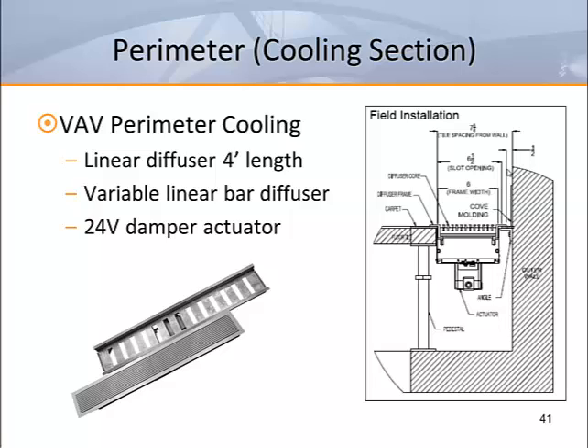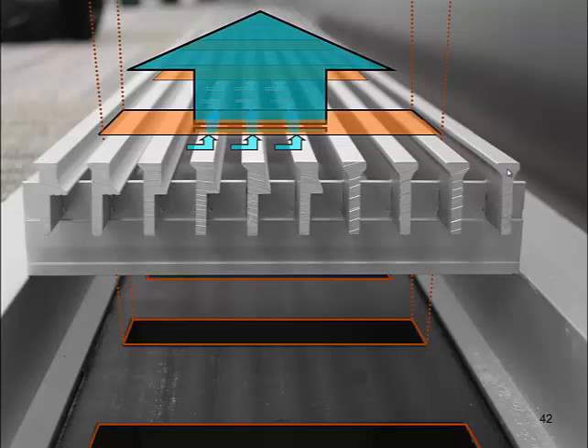When fully open at 0.07 inches of plenum pressure, this unit delivers 225 CFM to the space with a throw height of just 6 feet above the floor. As the supply air is delivered through the transverse aperture shown in this picture, the room air is induced into the supply air and mixes. This induction process and mixing keep the supply air jet from gaining momentum to create long throw.